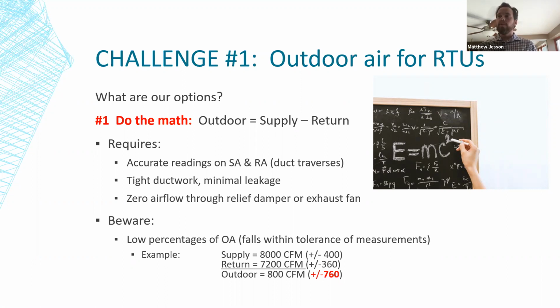So when you do the math and come up with your outdoor air, that's 800 CFM of outdoor air plus or minus 760, which basically might tell you you might be double what you think you are, or you might be almost nothing. Now, I'm sure that somebody who's better at statistics could really tear into me for how I'm adding together the uncertainties, but I think the general idea is valid. I call this trying to control small numbers with big numbers. It's difficult to do, and it can throw you off a lot.